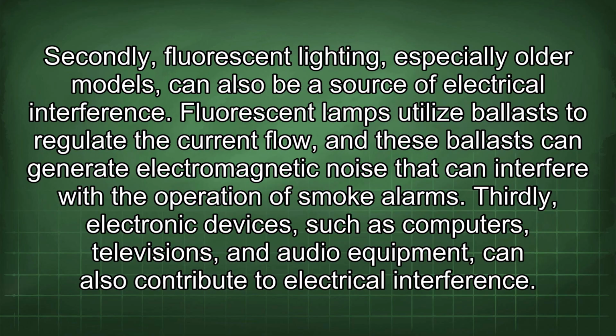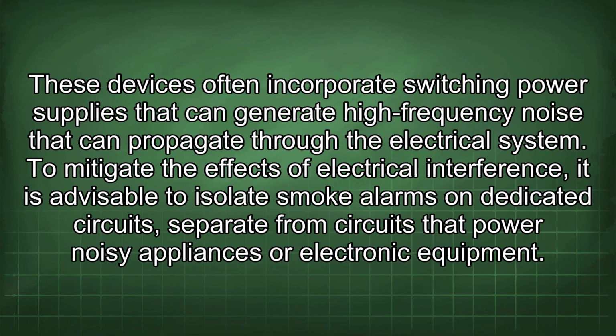Secondly, fluorescent lighting, especially older models, can also be a source of electrical interference. Fluorescent lamps utilize ballasts to regulate the current flow, and these ballasts can generate electromagnetic noise that can interfere with the operation of smoke alarms. Thirdly, electronic devices, such as computers, televisions, and audio equipment, can also contribute to electrical interference. These devices often incorporate switching power supplies that can generate high-frequency noise that can propagate through the electrical system.